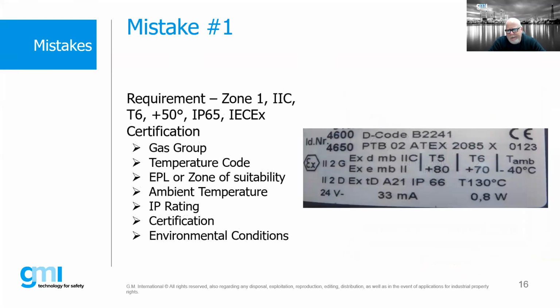So looking at another nameplate, if you will. The requirement again is Zone 1, IIC, T6, +50, IP65, and we need IECEx certification. So what do we see with this particular one? Again, in this case, it's ATEX only. There are some things on here that were okay as far as potential ambient. We see some T codes on there. Without going into all the details on how to read the label, we see that with +80 we get a T5, and we get a +70 rating at a T6. So we do meet the +50 degrees C, but we don't see any IECEx certificate or labeling, and that's one issue. So again, these are things that we usually would catch at a very, very early stage, right?